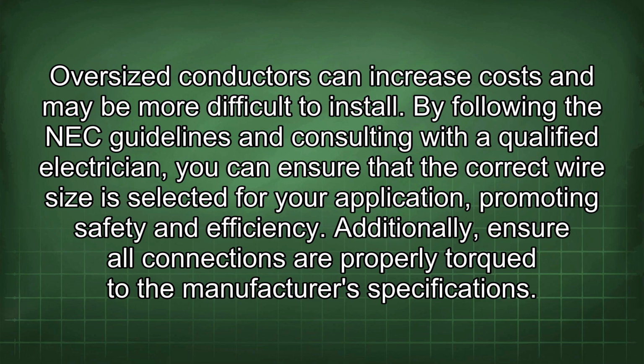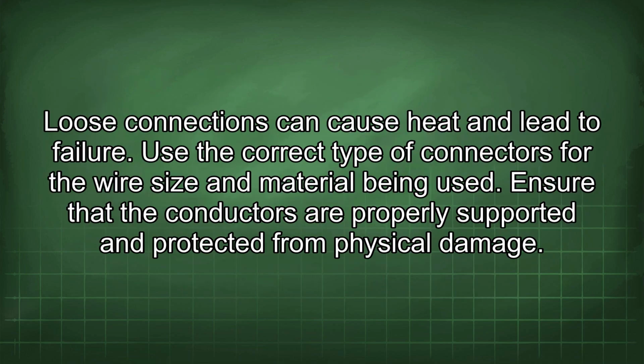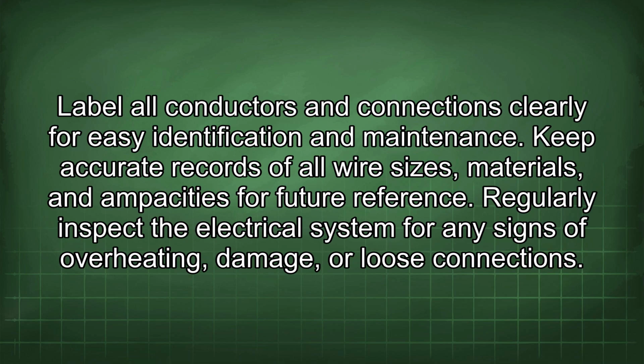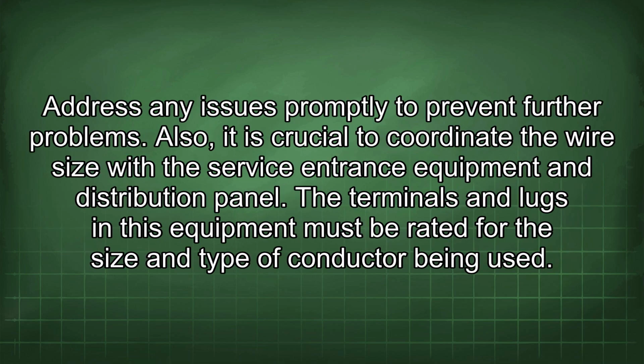Additionally, ensure all connections are properly torqued to the manufacturer's specifications. Loose connections can cause heat and lead to failure. Use the correct type of connectors for the wire size and material being used. Ensure that the conductors are properly supported and protected from physical damage. Label all conductors and connections clearly for easy identification and maintenance. Keep accurate records of all wire sizes, materials, and ampacities for future reference. Regularly inspect the electrical system for any signs of overheating, damage, or loose connections. Address any issues promptly to prevent further problems.